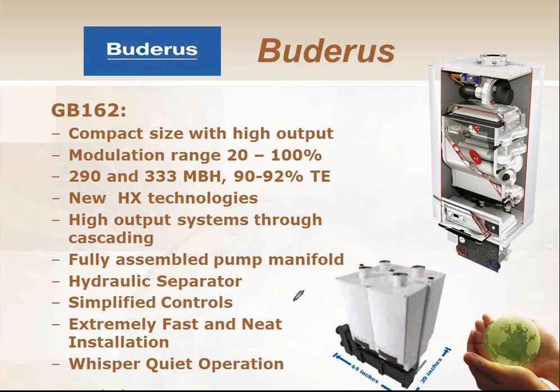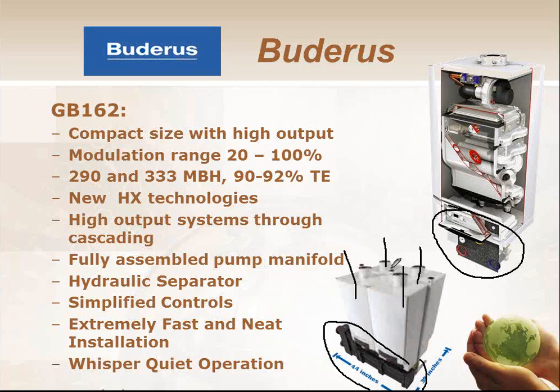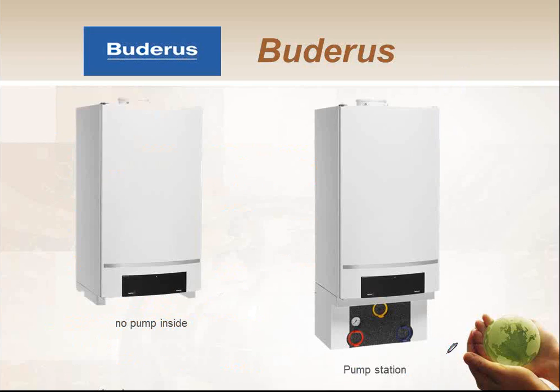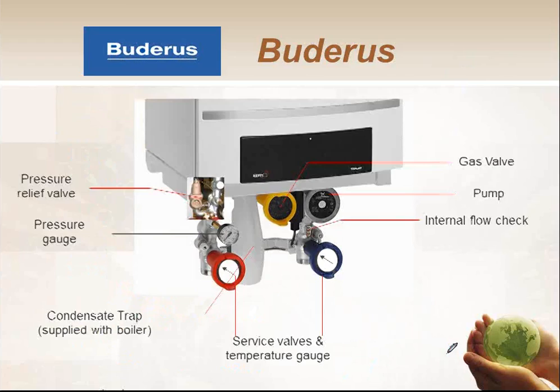But the nice thing about this one is you can get the piping packages built into this guy as well. It's an optional thing. And you can even get piping packages for multiple boilers getting together. So this one here has 4, I believe, 333,000 BTU on here. So that's 1.4 million BTUs, all manifolded together from this factory kit on the bottom here, pumping built in. And it's all fitting in 44 by 39 inches. So it's pretty tight to get it all in there. So you can get it with or without the pumping built in.